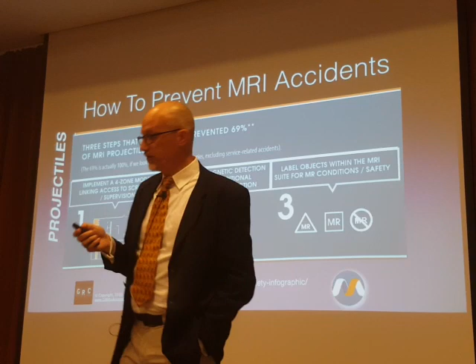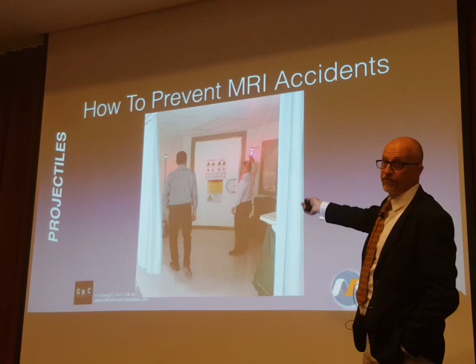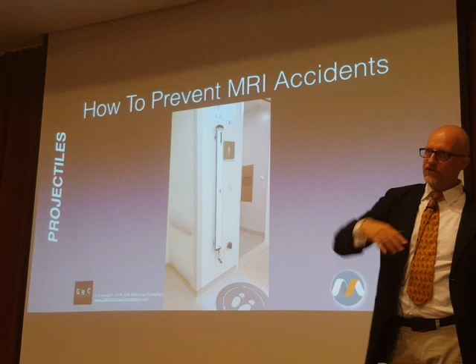This is an example of the Metrosense ferromagnetic detection system, the type that's mounted outside the doorway. Here's a different view, a different installation. In addition to the ones at the doorway, there's what's called a screener system that is typically installed where you prepare the patients in your zone 2 environment. My recommendation is that the screener type of systems are close to where you have your changing rooms and your patient lockers, so that when you discover something, you don't have to back the patient all the way up from the magnet room back to wherever the changing and screening areas are. This just is a part of that process. So anything you do discover, you're just right there, you put their belongings in the patient locker.